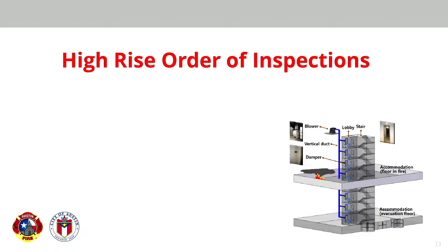Stairwell pressurization testing - buildings over 75 feet are required to have stairwell pressurization. These are all going to be conducted by a third party that has been approved as a vendor by the Austin Fire Department. There's quite a few of them - if you need a source, let me know, I've got a list. If it's somebody we work with a lot, we may or may not be there to witness their procedures for the stairwell pressurization. If it's somebody from out of town that we haven't worked with, we're probably going to want to be there for at least a couple of hours.